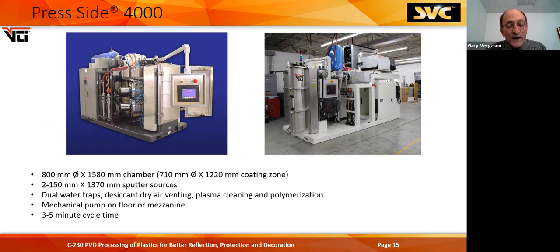Mechanical pumps are located either on the floor or on a mezzanine like you see here. And one of the key things that we learned early on, the closer we could put the roots blower to the vacuum chamber and have a little bit of a vacuum accumulator between the roots blower and the mechanical pump, sped up that roughing time. So these machines, a little over a cubic meter in volume, pump from atmosphere to 100 millitorr in about 25 seconds. So it kind of smokes. In this machine, depending on your maintenance, cycles run door to door in 3 to 5 minutes.